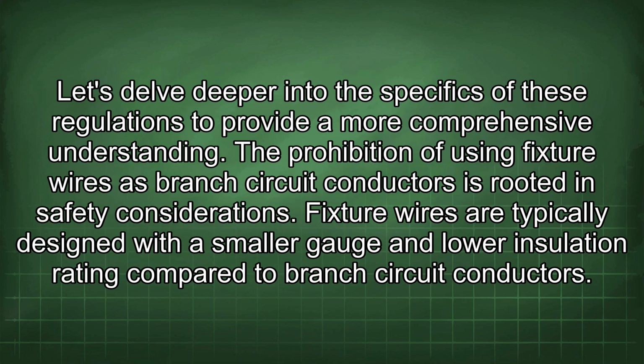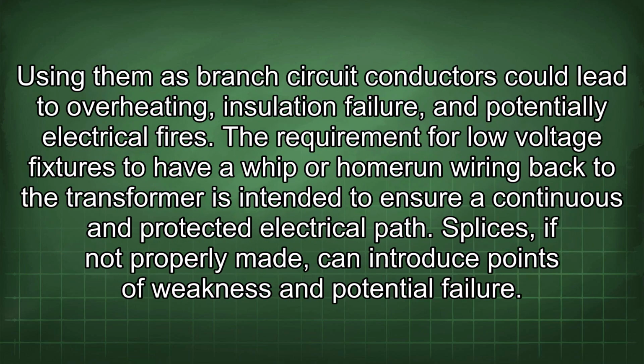Let's delve deeper into the specifics of these regulations to provide a more comprehensive understanding. The prohibition of using fixture wires as branch circuit conductors is rooted in safety considerations. Fixture wires are typically designed with a smaller gauge and lower insulation rating compared to branch circuit conductors. Using them as branch circuit conductors could lead to overheating, insulation failure, and potentially electrical fires.